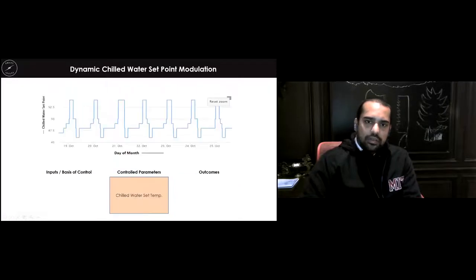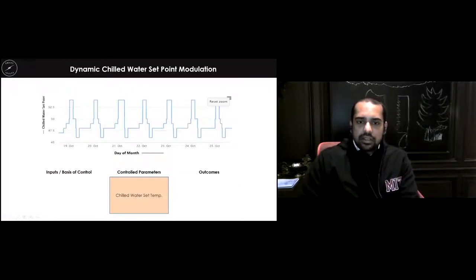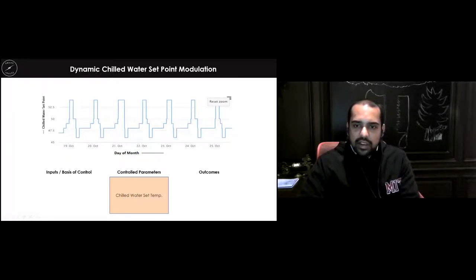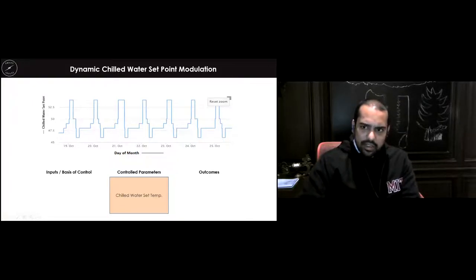Another example is if you look at chilled water set points. This is the actual chilled water set point history for one of the sites. So this is being controlled. Now, again, you can see that the generic shape is the same, but if you look in detail, every day chilled water set points are different. The shape of the curve is slightly different every day because there are a number of inputs.